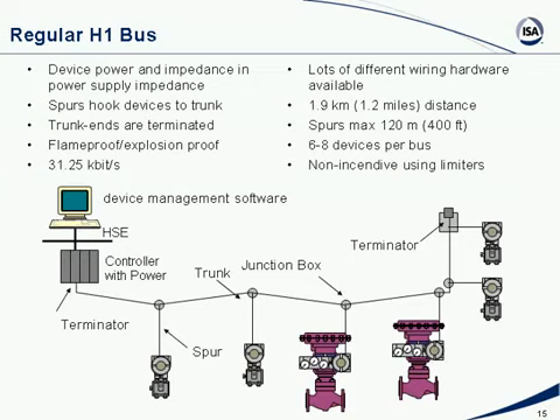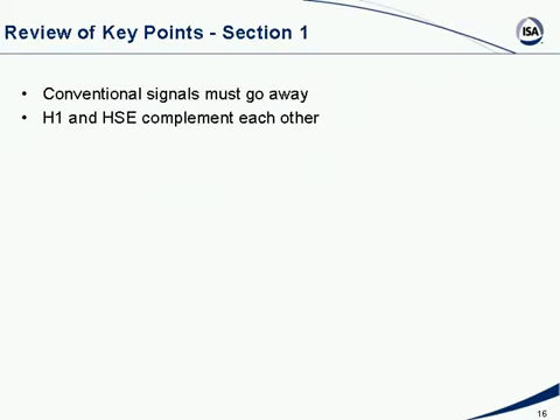About grounding, it's quite easy. You ground the shield, and you do so at the power supply end. You cannot ground the field bus signal itself, the field bus wires. You always ground only the shield, and only at the power supply end, never at the device. All right, we have come to the end of section 1, so I will go through the key points here.